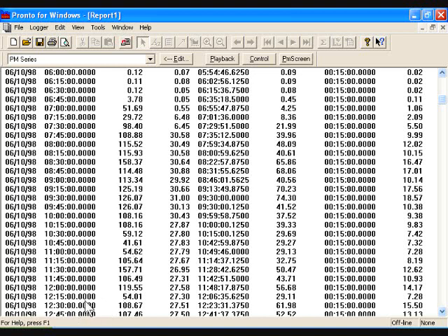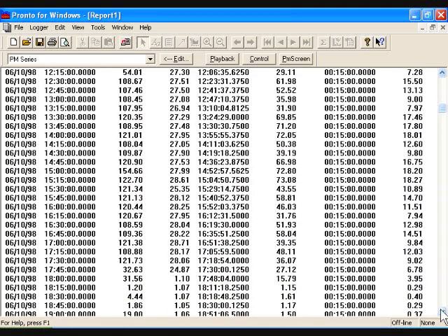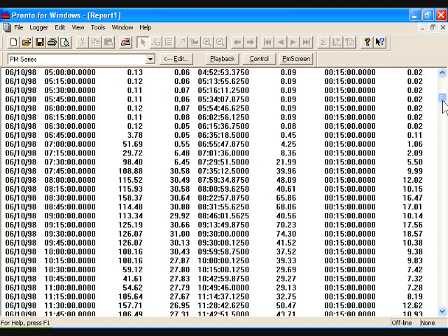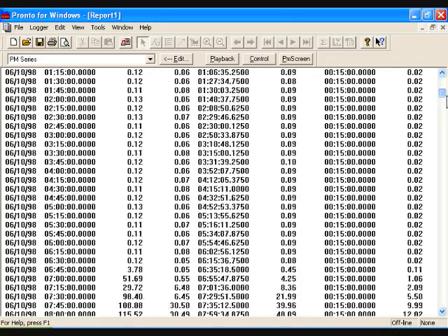Then if you continue on down, you can see at 12:15, that 15-minute period, for some reason, maybe a portion of the assembly line went offline, or they stopped it to retool or reset, and the demand went down to about half. If we scroll down further, you can see at the end of the day, when they were shutting down, and then they went home. So it's a very telling tale that you can see here through this demand or interval report.